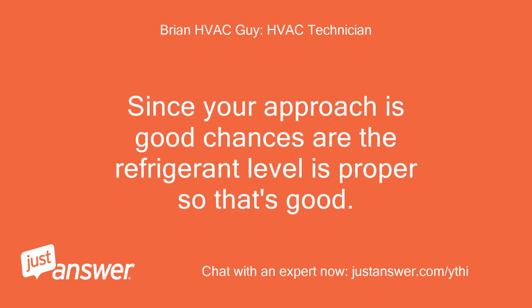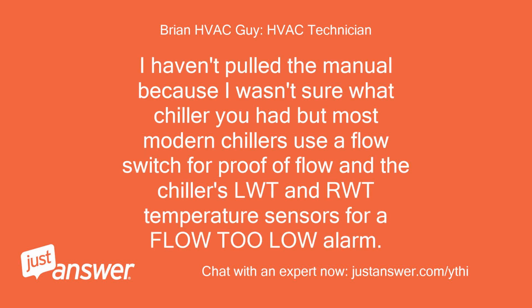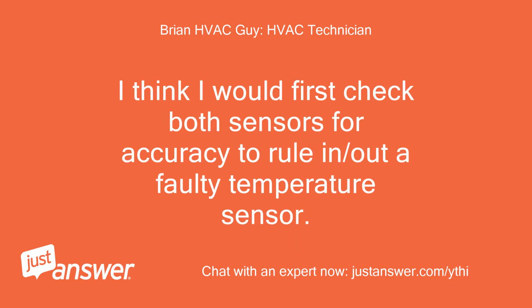Since your approach is good, chances are the refrigerant level is proper, so that's good. I haven't pulled the manual because I wasn't sure what chiller you had, but most modern chillers use a flow switch for proof of flow and the chiller's LWT and RWT temperature sensors for a flow too low alarm. I think I would first check both sensors for accuracy to rule in or out a faulty temperature sensor.